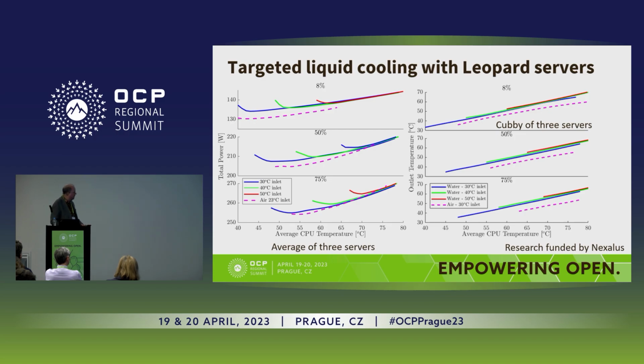We saw the same kind of behavior. Again, we saw the fact that there is a sweet spot of operation, as we dialed in. And how did we dial in the temperature of the CPU this time? We had control of the pump that's pumping the coolant to the heads. So we can dial in a temperature, and it maintains that temperature of the CPU. And then we could read off the power consumed. And what you can see, the difference between 30 degrees, 40 degrees, and 50 degrees, this is actually the temperature of supply to the IT. Obviously, when you're running at 50 degrees, you can't ask the CPU to run at 50 degrees as well, because 50-degree water on and asking for 50 degrees from the CPU is not physically possible.